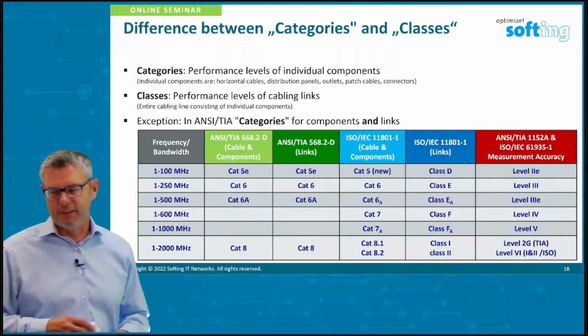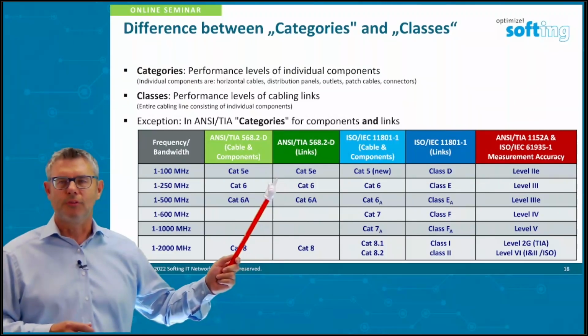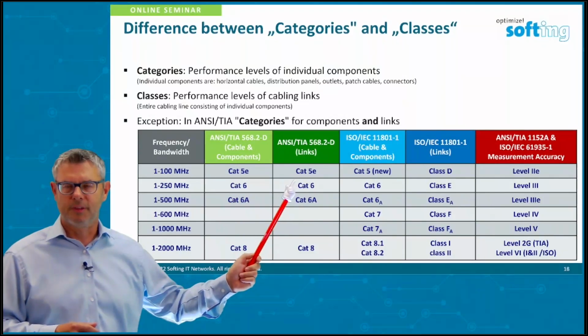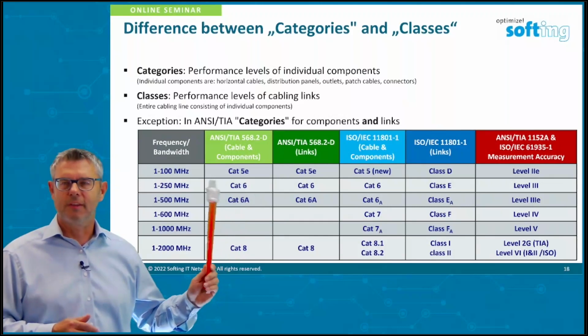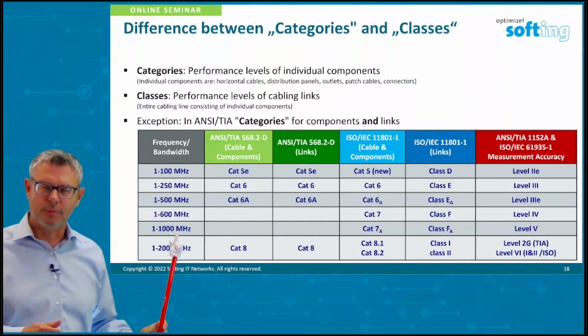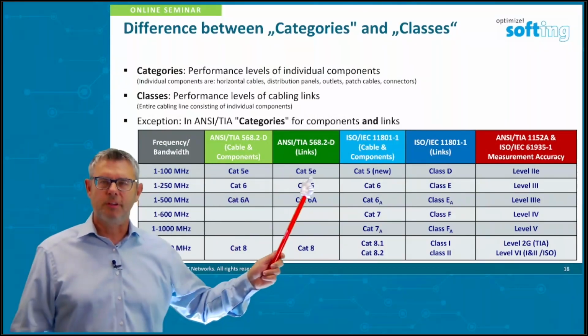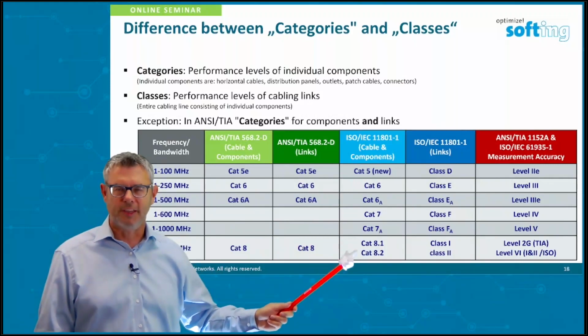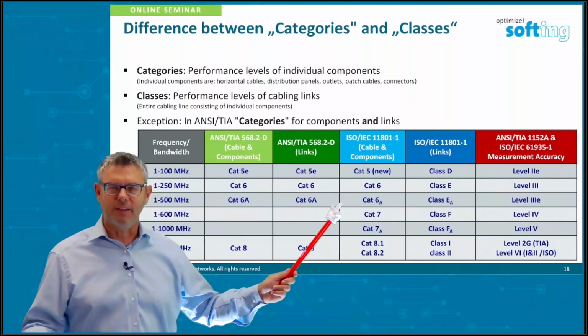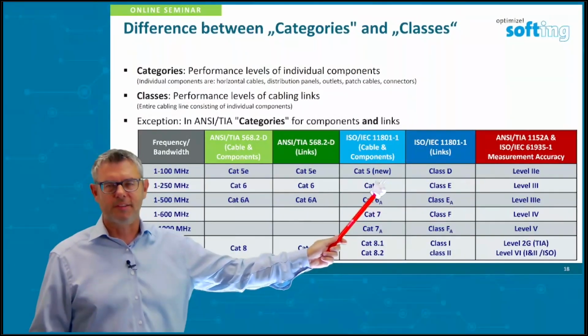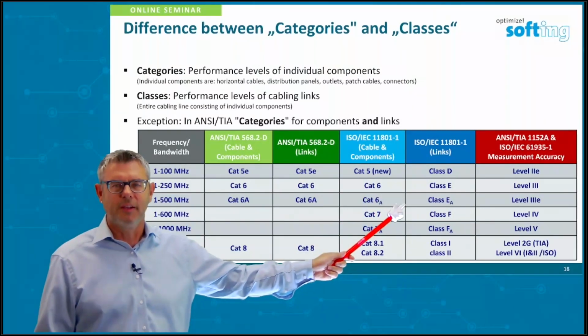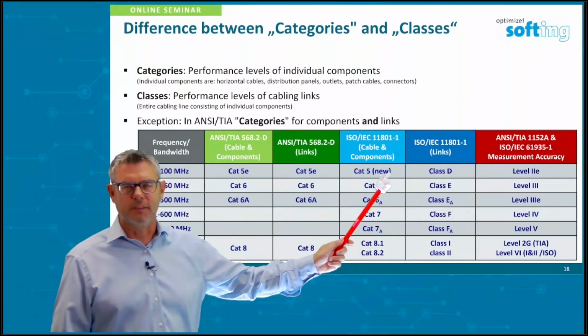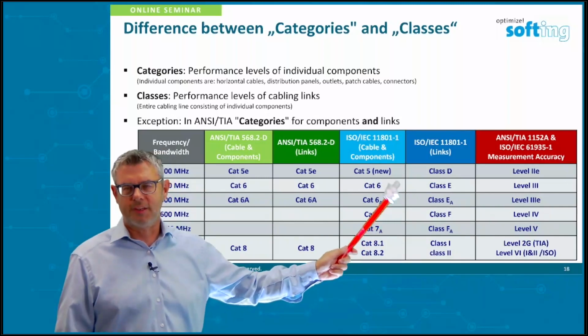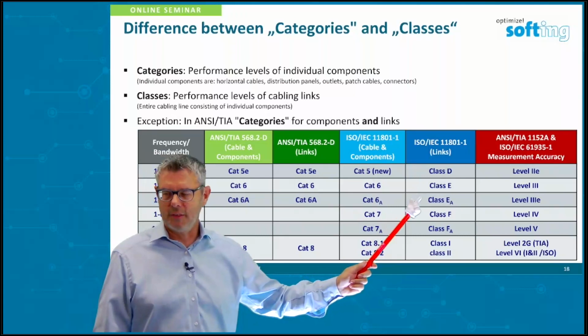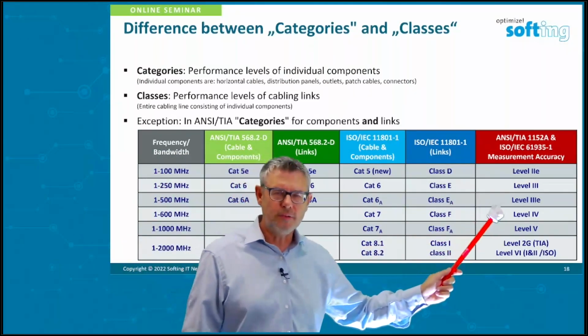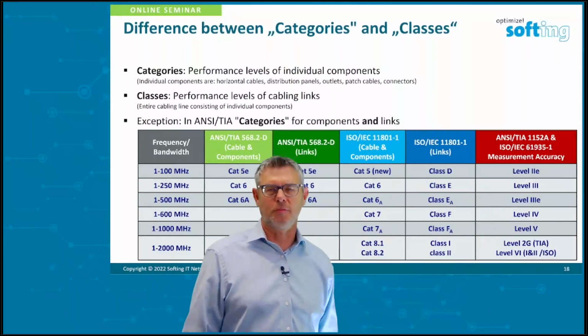This link is usually tested, in our area of Germany and Europe, against a performance class. The American standards use the same expression, category, for both components and links. The numbering is oriented on the performance bandwidth level of the part or link. International standards also have categories for components, but when testing a complete link, we switch to classes, combined with letters: D, E, EA, F, FA, and some Roman numerals for 1 and 2. So testing a link is always based on classes, and you must make sure to use an instrument that's properly accurate for this measurement - but that's detail we'll discuss next week in the advanced course.